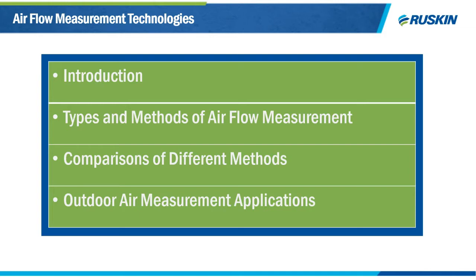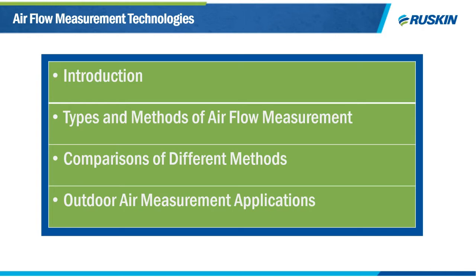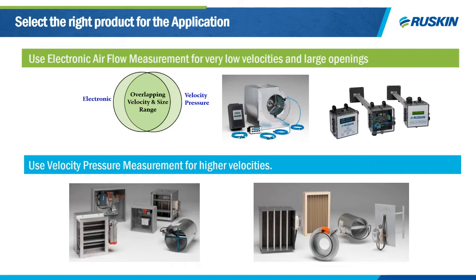Thank you, Ray. I'm Glenn Esser, and I've been asked to talk about types and methods of air measurement, comparison of different methods, and various outdoor air measurement applications, which as Ray explained are some of the most challenging. Selecting the right product for the application is key to success. Electronic or properly applied velocity pressure air measurement devices can be equally accurate. In general, electronic works best for lower velocities and large openings, and velocity pressure or electronic can either be applied for higher velocity applications.